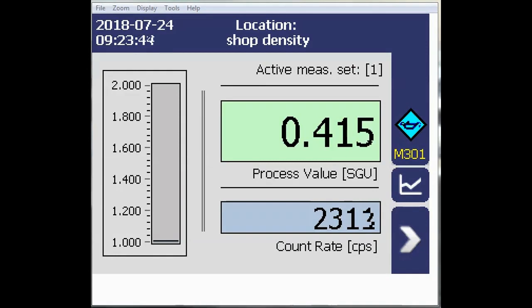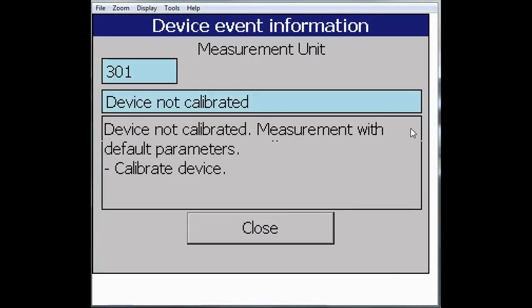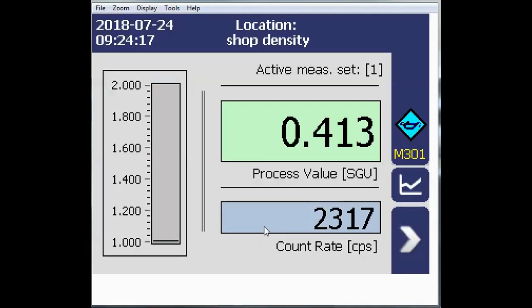LB474 1-point quick calibration. Note, this is intended for performing a calibration on an already operational gauge. If you have a new gauge that has not had the basic set of parameters entered, please do so first. You'll notice on the home screen of this display, on the right hand column, this blue label, if we click on it, is where any issues that your gauge has will be noted. You notice this one, the device is not calibrated.